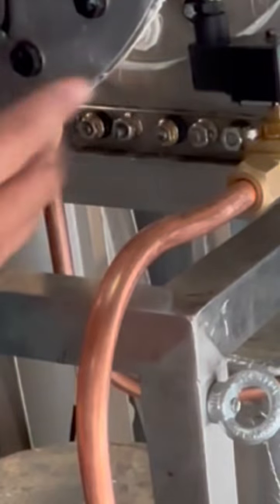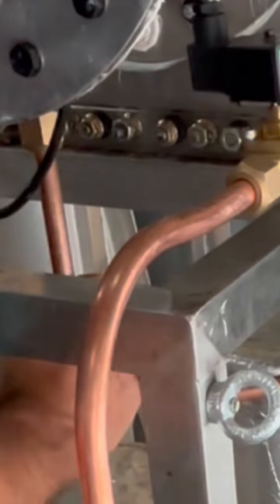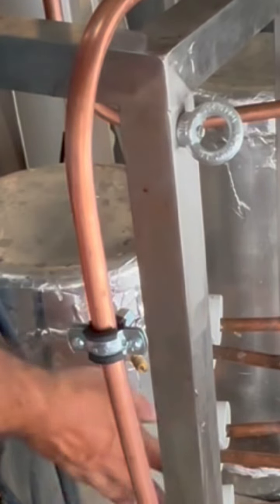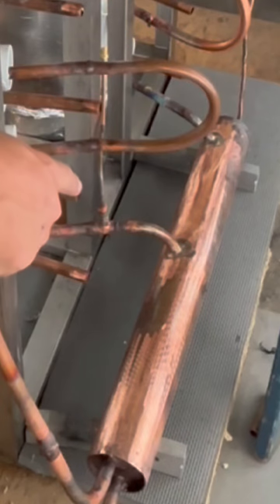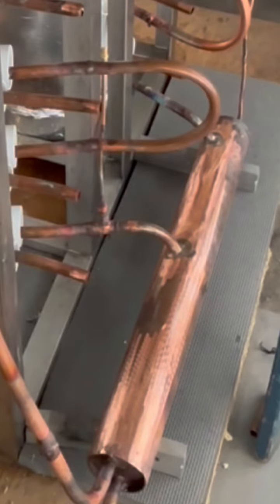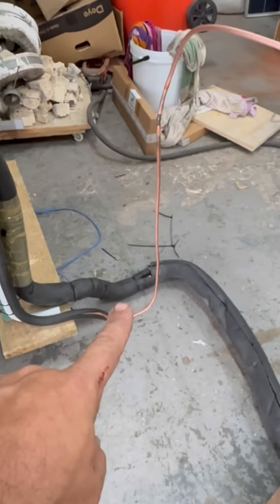After the Tesla turbine, it goes out the exhaust to the counterflow heat exchangers, and then to the accumulator. From the accumulator it goes back through a zigzag pipe that runs across here at floor level, both high pressure and low pressure.